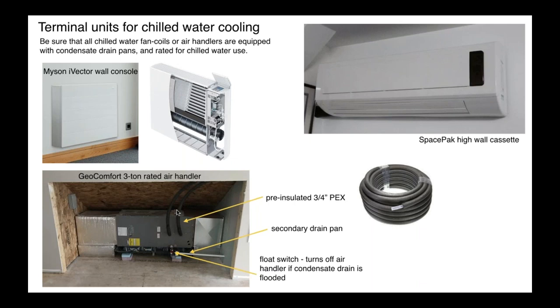Very important, make sure your line set, your chill water pipes back to the mechanical room, are insulated and vapor sealed. Now, we could have done this with copper. We could have bought PEX and slid pieces of insulation onto it. We elected to just go with pre-insulated 3/4 inch barrier PEX. This happened to be from Uponor. There may be other sources of it out there. It ran about $2 a foot. I think it's well worth it.